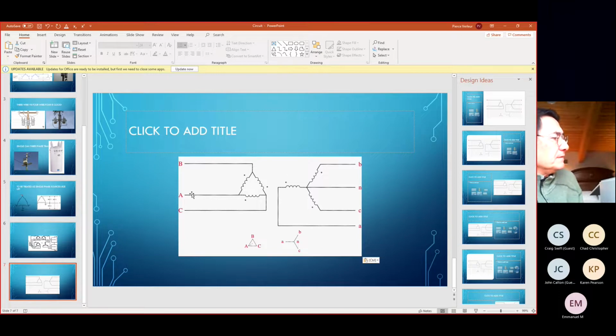In the case of the delta, if this is a delta primary and then there's a delta secondary, I've seen those type of situations as well. That's an ungrounded delta, and again, if you don't see 4 lines coming off the power pole, that is a potential configuration. And again, you need to take into account the corrective action is really quite simple. You need to find that connection, and they have a note in the back of the ABB manual that will tell you how to disconnect that ground connection on their EMC filter. And then you're okay.